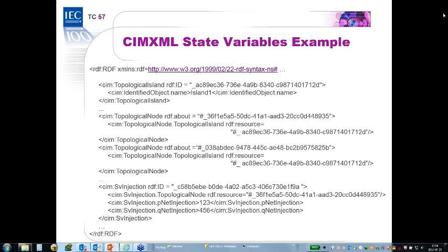Definition of a model part. Now this is a definition that is a bit still in the works, but the principle here is supported currently in the CIM. A model part is a set of CIM data that can be composed with other model parts to create a complete model. And then it says there can be any number of instances of a given model part that are usually referred to as versions. This is usually used to just track as-builts. As new construction completes, you create a new version of the as-built. And a model part has a model part specification, and this basically describes the information about what the model part is for.